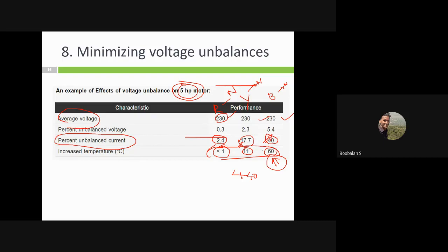So what do we do - we need to give a separate parallel current path, around 60-70 amperes, 40 plus 20 is 60 ampere total current. So every phase needs to contribute around 20 ampere each - this one 20, this one 20, this one 20. That's how current flow should be, so this becomes a good balanced motor. If instead it stays at 40-20 unbalanced, the motor will definitely lead to failure.